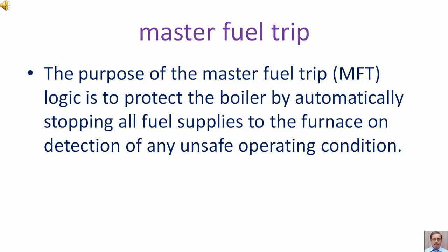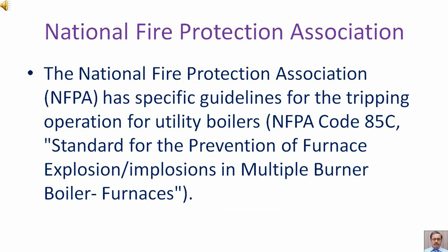The purpose of the master fuel trip is to protect the boiler by automatically stopping all fuel supply to the furnace on detection of any unsafe operating condition. The National Fire Protection Association has specific guidelines for the tripping operation for utility boilers. That is the standard for the prevention of furnace explosions and implosions in multiple burner boiler furnaces.